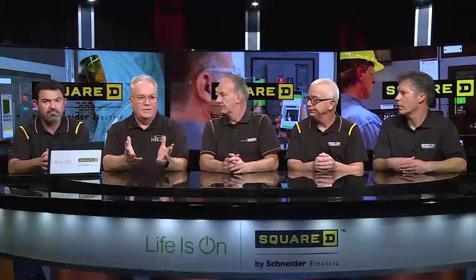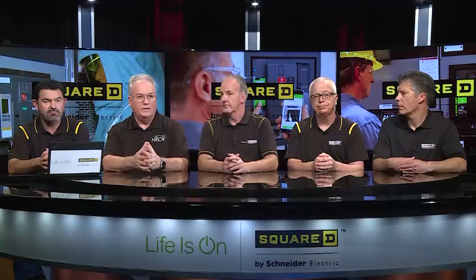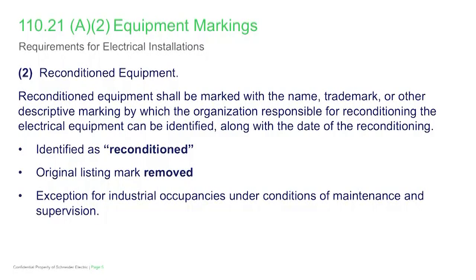The process of reconditioning equipment is not new to the electrical industry. It just started being identified in the NEC in the 2017 cycle, the first phase of evolving the NEC to address reconditioned equipment and those processes. It started in 110.21(A)(2) with a general requirement that equipment be marked with the name, trademark, or other descriptive mark of the organization responsible for the reconditioning, along with the date the reconditioning process happened. So it needs to be identified as reconditioned in accordance with those marking requirements, and the date has to be applied.